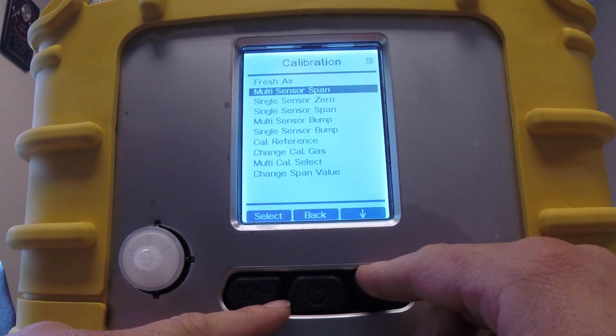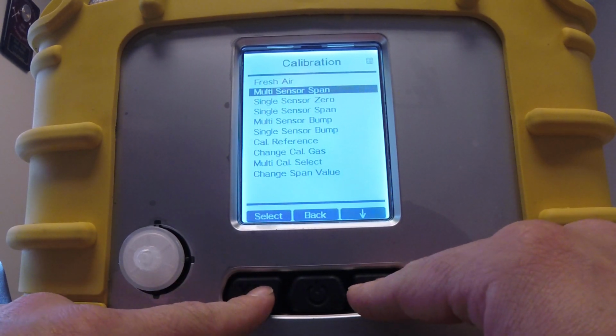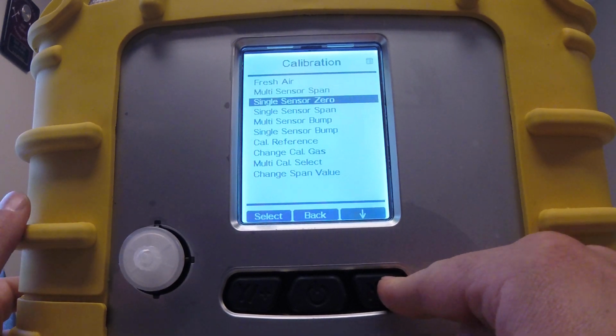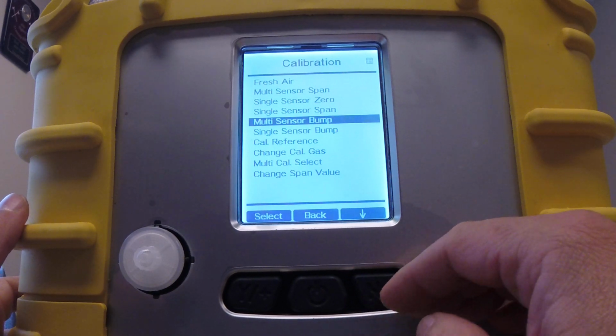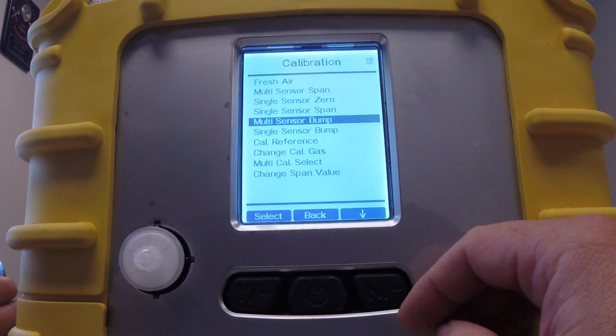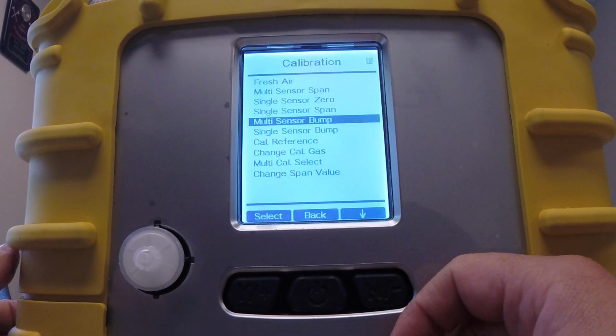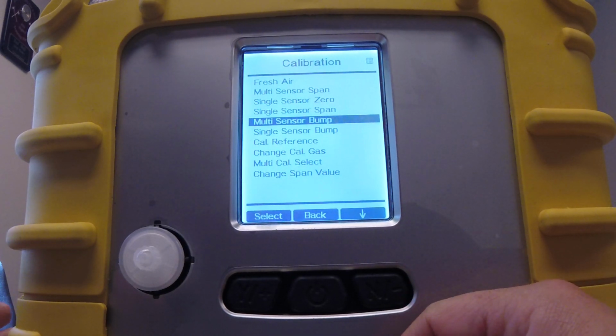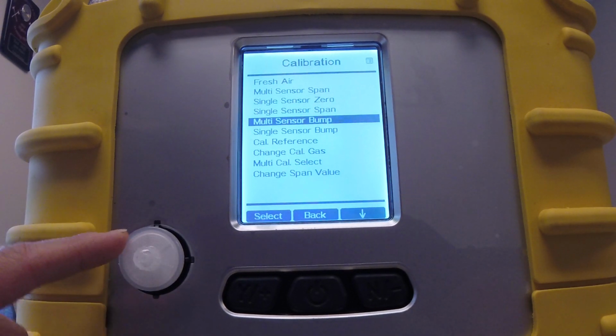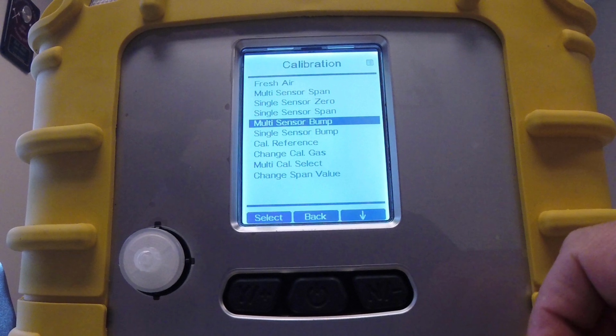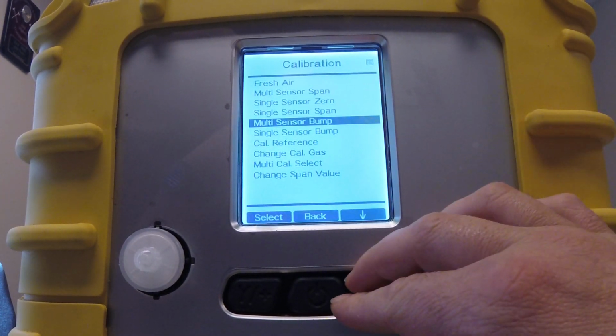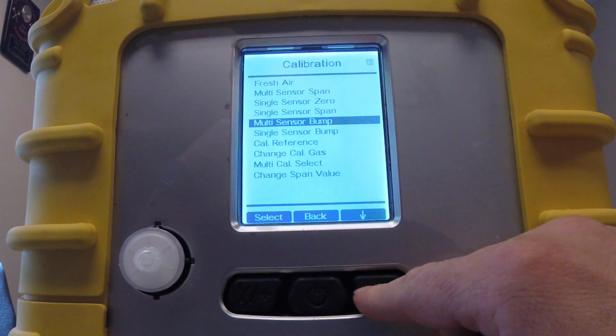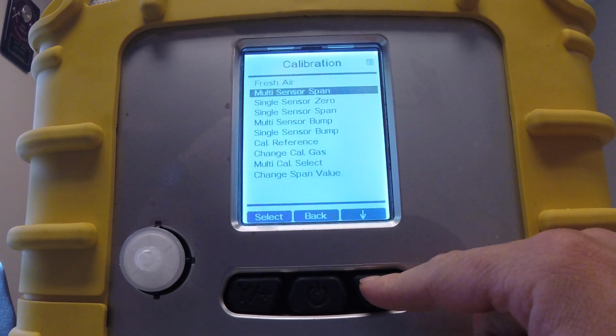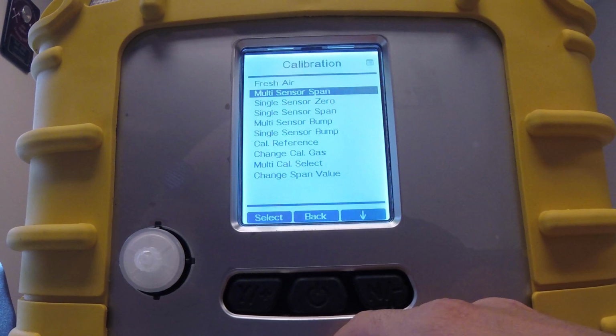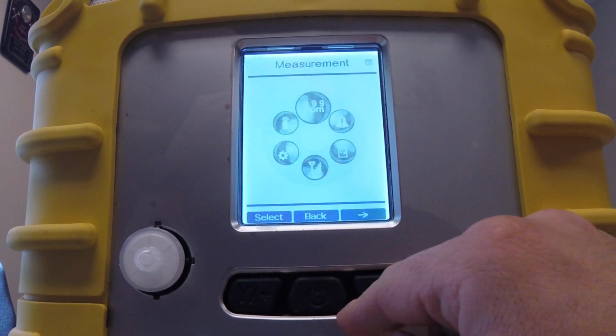So we're now reading zeros, 21.1, so we're elevated in oxygen. At least we know we're healthy in this room. Run for days. So this also gets into our single sensor stuff, multi-sensor bump. So that's where we would hook it up to our gas. In this case, we have to hook it up to the isobutylene as well to calibrate the VOC, and there's a tubing in the box with the machine that allows for that. You're going to hook up to this port here, that's your intake essentially. So that'll be for the bump test for the multi-sensor, and then there's the multi-sensor span calibration if for whatever reason we haven't kept this thing up with routine maintenance, that we may need to do that, but we shouldn't need to.